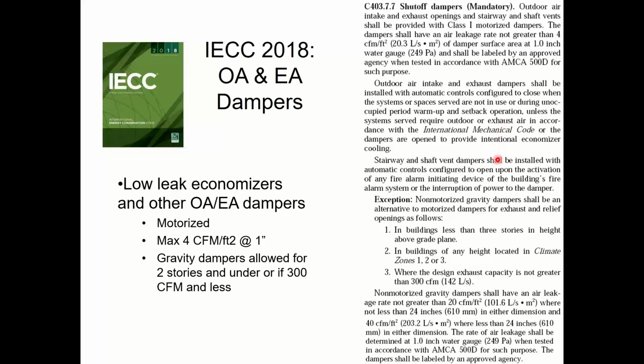Once again, California Title 24 code does not comply with this. Title 24 has a thing called a low leak damper. It is not low leak enough to be compliant with this. So once again, pay attention to that. Some of the manufacturer dampers, you'll ask them if it's low leak, they'll say yeah. You'll ask them if it's certified to be low leak, they'll say yeah, it's Title 24, bro, it's good. Yeah, but it's not compliant with IECC, meaning it's not AMCA certified. Not good enough. So we've got a couple examples so far where California is not as good as everybody else, per se.